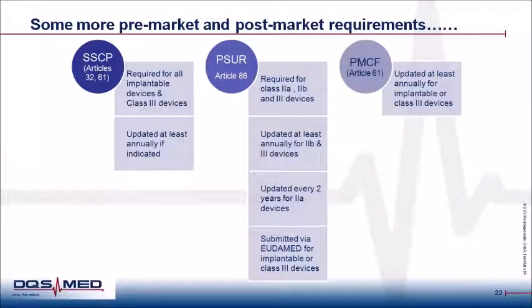So now let's move on to some more requirements which are posed by the MDR. For the manufacturers, not just classifying the device into the respective risk classification, the manufacturer also has additional pre-market and post-market requirements before he or she can apply for a certification. That is, namely, a so-called SSCP report. It is an abbreviation for summary of safety and clinical performance. This plays an important part of the very strong post-market follow-up required by the MDR for implantable and Class 3 medical devices. This report is intended to provide the healthcare workers and relevant patients access to current clinical data and other information about the safety and clinical performance of the medical device in question.